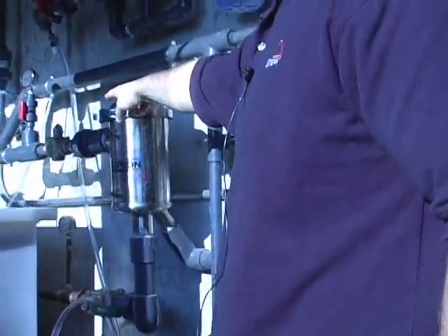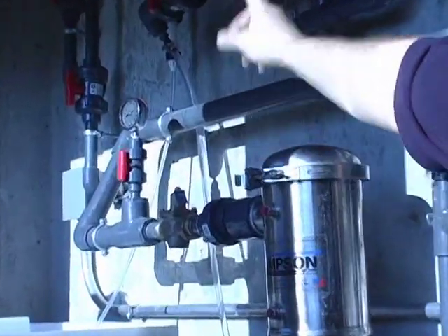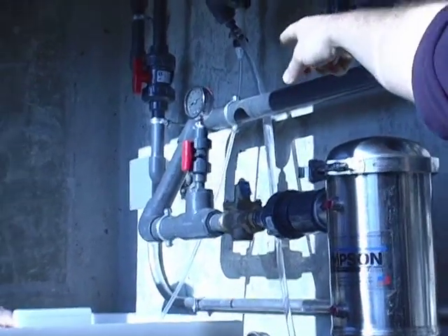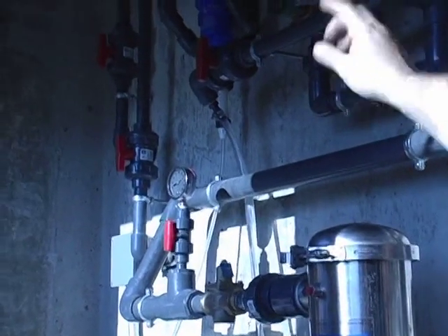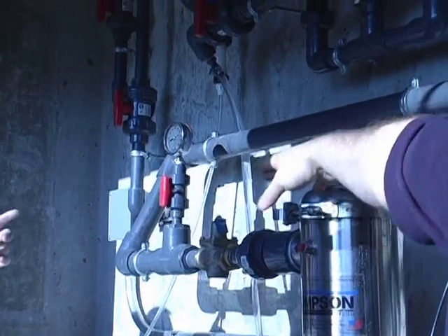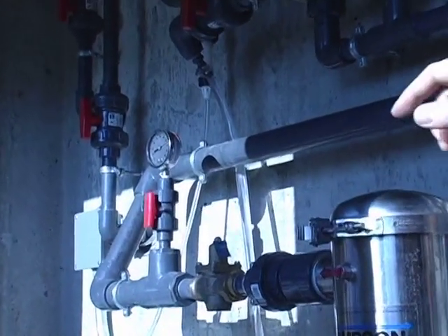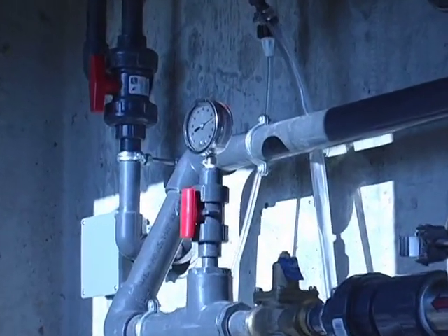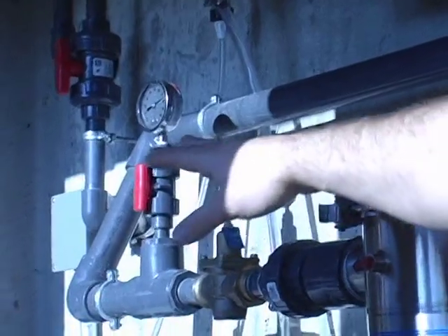You have your pressure reducing valve there that's set at 50 psi. You have a pressure gauge there where you can monitor if you're getting any spikes in pressure. If for whatever reason you see that go above 50 psi, like it is now, that's static. Once you open it up, the pressure reduces greatly. You can adjust it then.